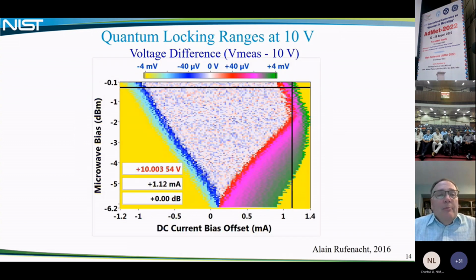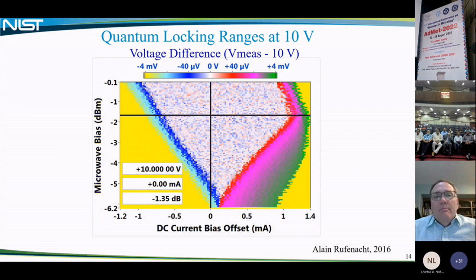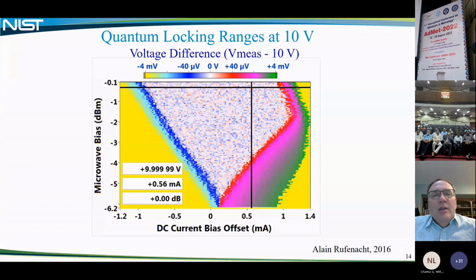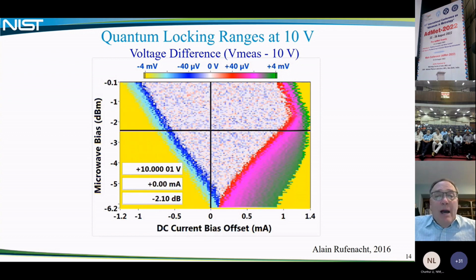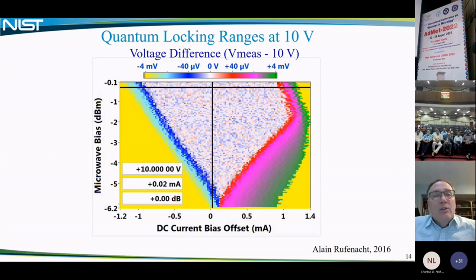Here's an example also of the DC current bias quantum locking range. You can see that over this few milliamp range, it is also quantum locked. The color scheme is the difference voltage from 10 volts of the measured 10 volts being generated. And we also are changing the bias for the microwave power, because that is another bias condition that has a quantum locking range. So this is true for all of these Josephson voltage standards.